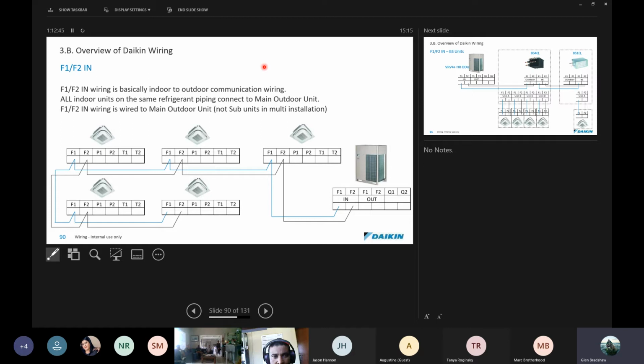Okay, so the overview of the wiring. Okay, so this is a standard type installation. One condenser with a couple of indoor units. You'll see the F1, F2 in the outdoor unit. You will see F1, F2 in, F1, F2 out, and Q1, Q2. Okay, with a single compressor, we're not going to use Q1, Q2, but we have F1, F2 going to the indoors, and each unit has an F1, F2, P1, P2, T1, T2. And we then daisy chain through the F1, F2 loop in the following sequence. Okay.